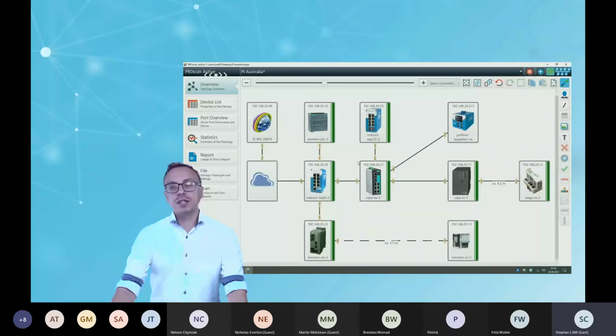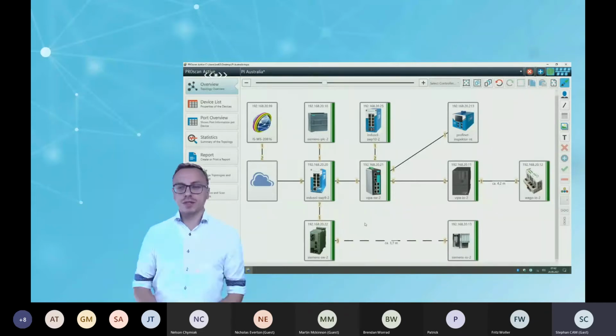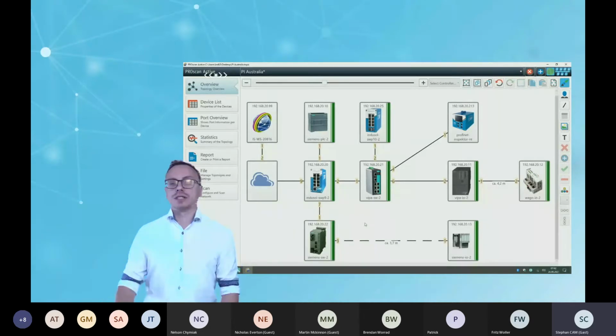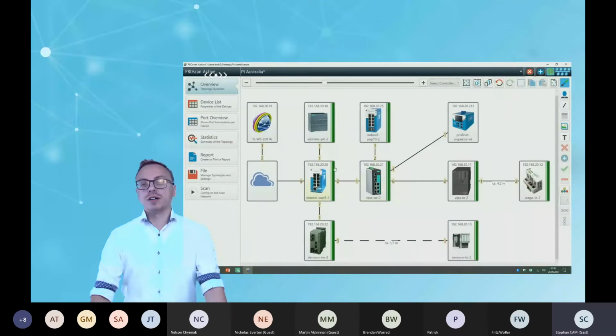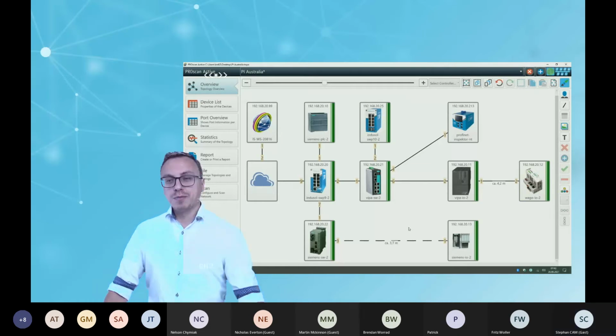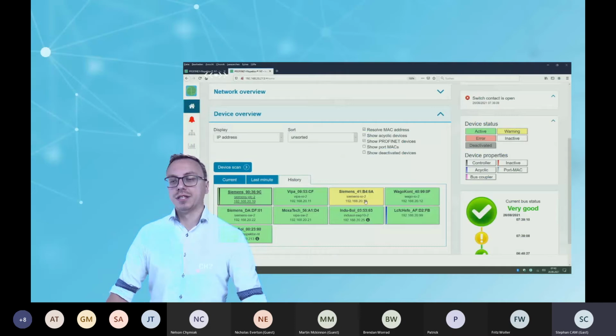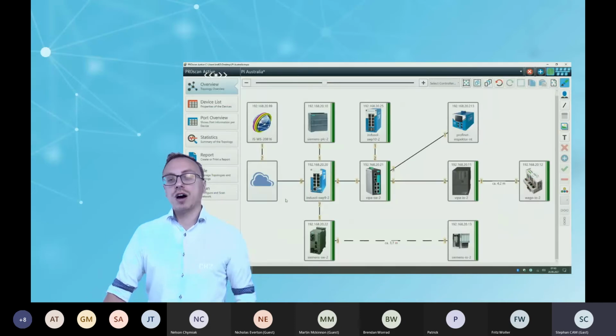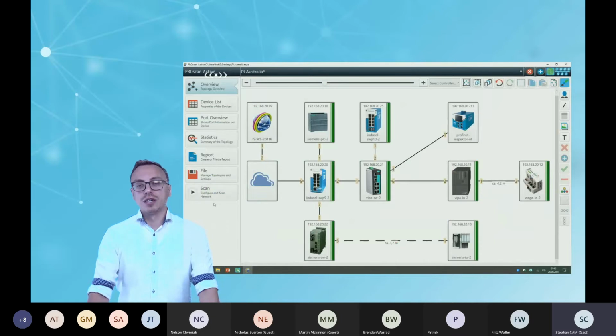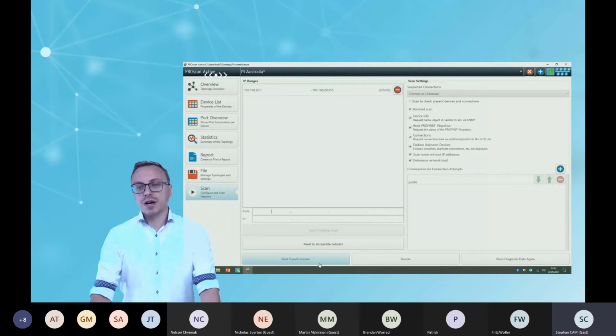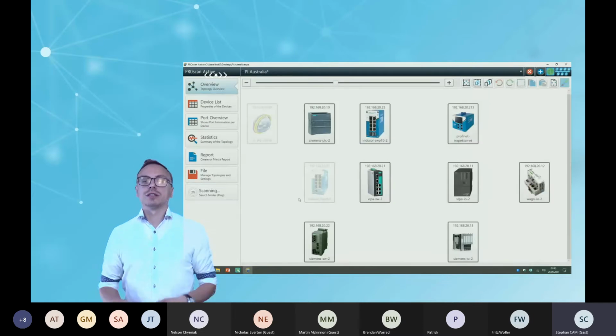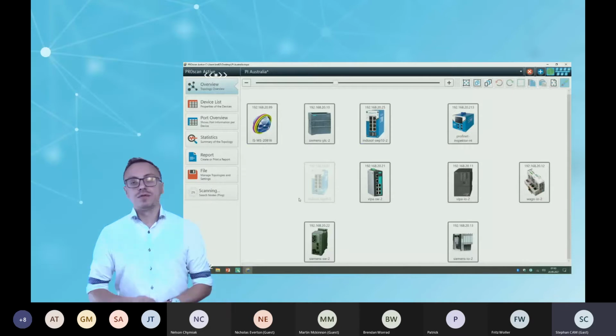But as I say, the important thing, if you have some problems in the system, you want to know where these problems are in your system. And here in this software you see some green bar charts, and this green bar chart shows you the situation as you measured or as you analyzed with ProScan Active. And now in this situation, every device was green. But if you look now at the inspector, we know something happened in the past. And now we want to know where these issues are in our topology. In this case, you can go to scan, you can make a comparison. We press on this comparison, and now this software should look for changes.